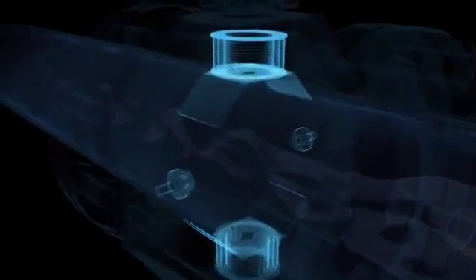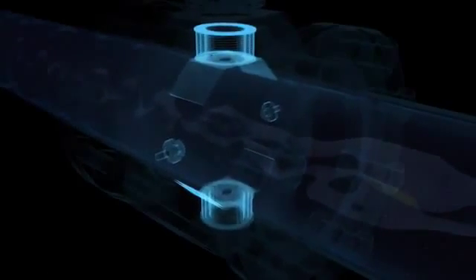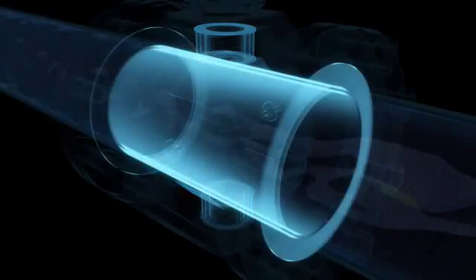Two electrodes, which can pick up electrical voltages, are installed at a right angle in the wall of the tube. The lining fitted on the inside wall prevents electrical short circuits between the conductive liquid and the metallic tube.